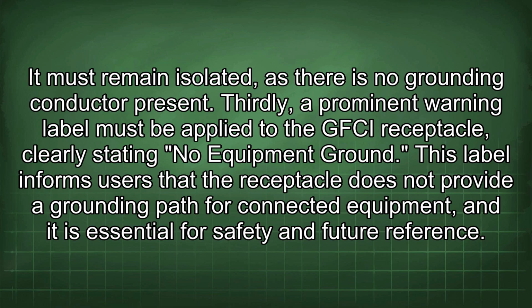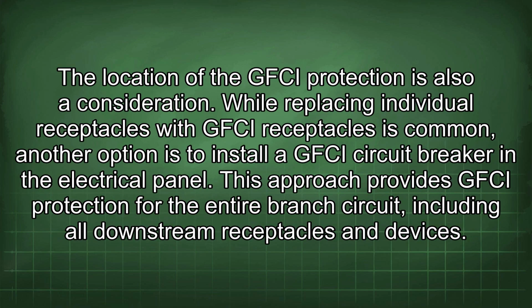Thirdly, a prominent warning label must be applied to the GFCI receptacle, clearly stating "No Equipment Ground." This label informs users that the receptacle does not provide a grounding path for connected equipment, and it is essential for safety and future reference. The location of the GFCI protection is also a consideration.